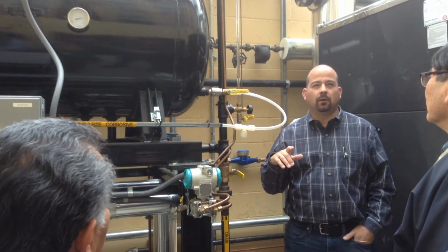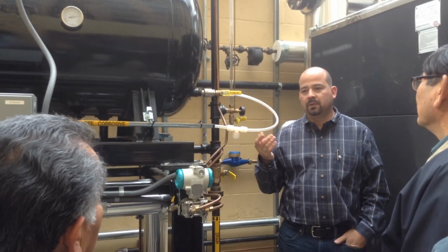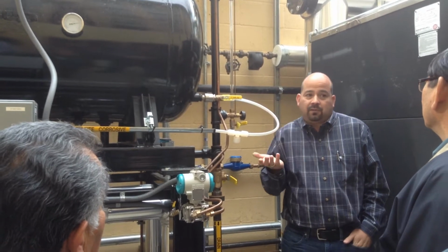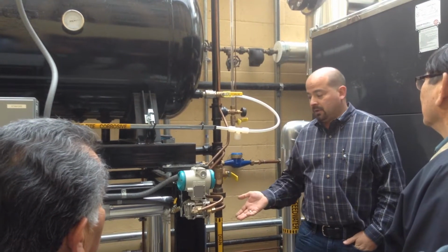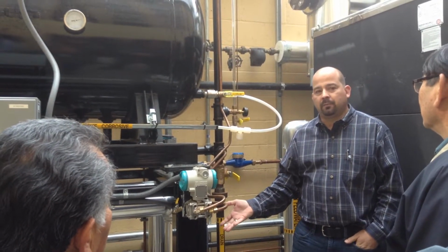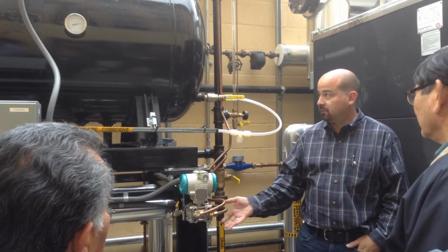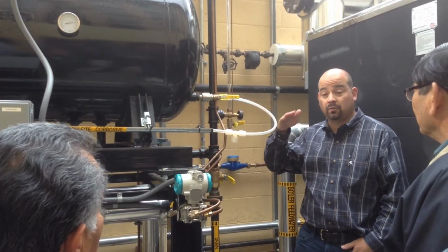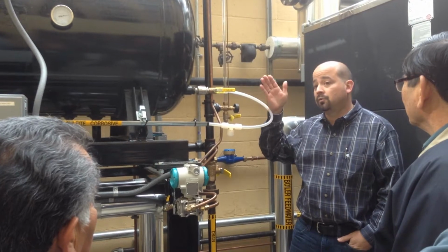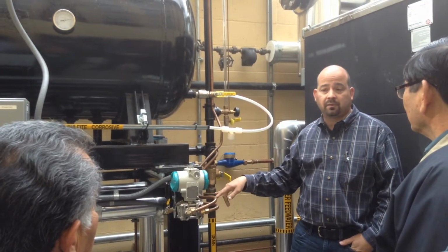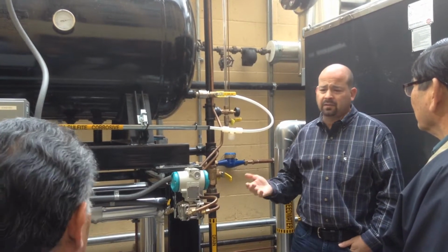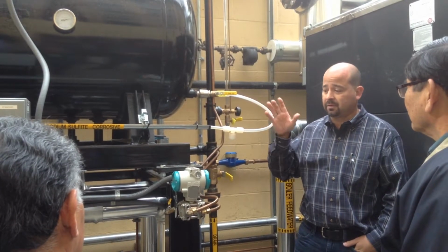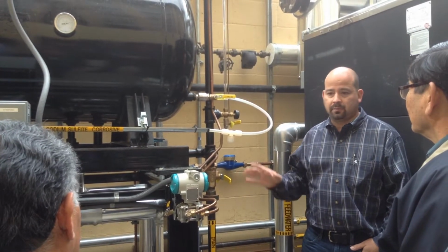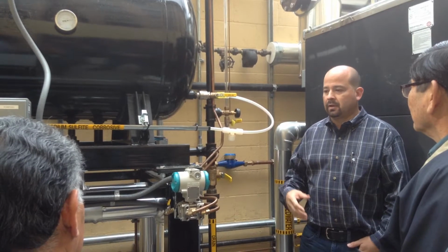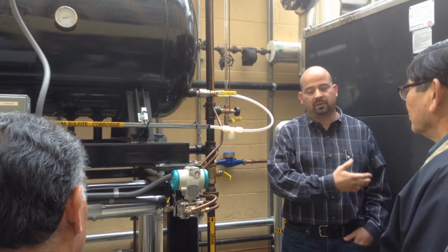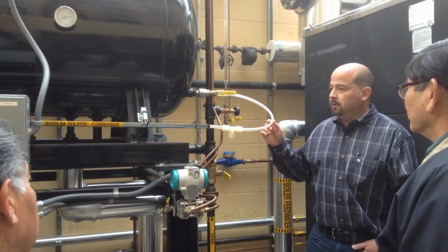Whereas if you had an open atmosphere boiler feed system, you can only get to 212 before you're boiling, but your pumps wouldn't be able to pump with that high a temperature. So these deaerators run anywhere from 212 to 220, 230, and the pumps will still pump to the boiler. And that's the most efficient way to do it. They're more expensive, but they're well worth their weight. You don't have to use as much chemical. You don't have as much oxygen to pit the boiler and potentially damage the boiler.